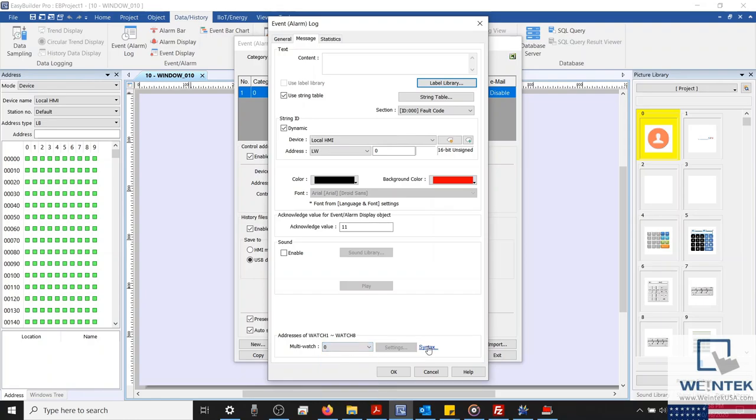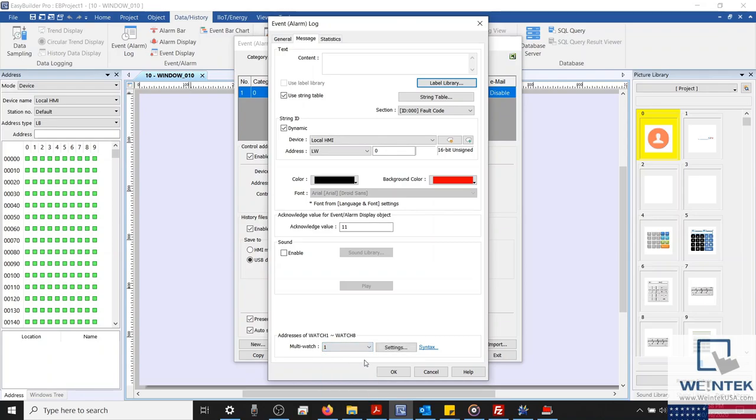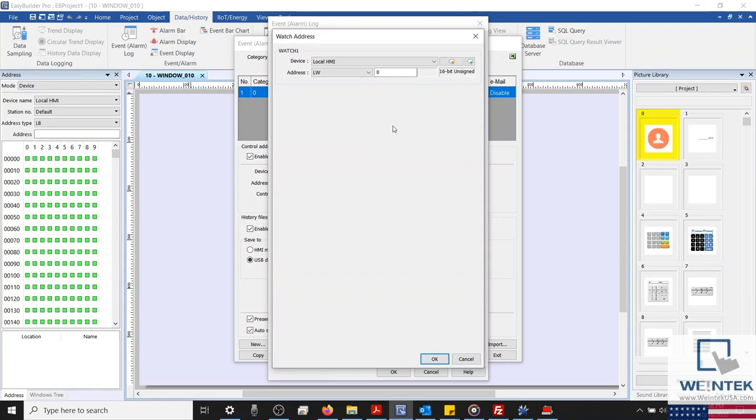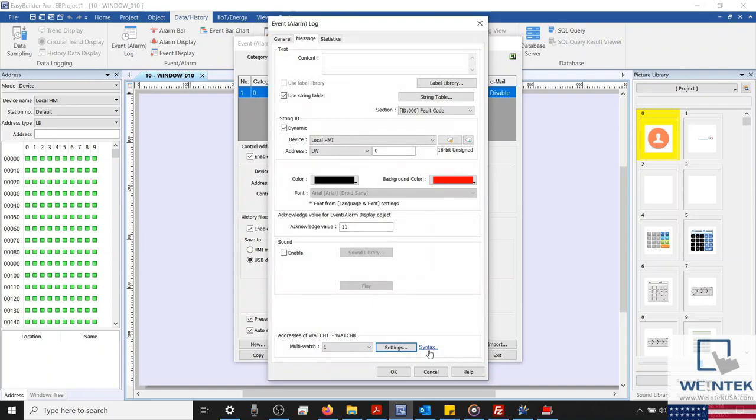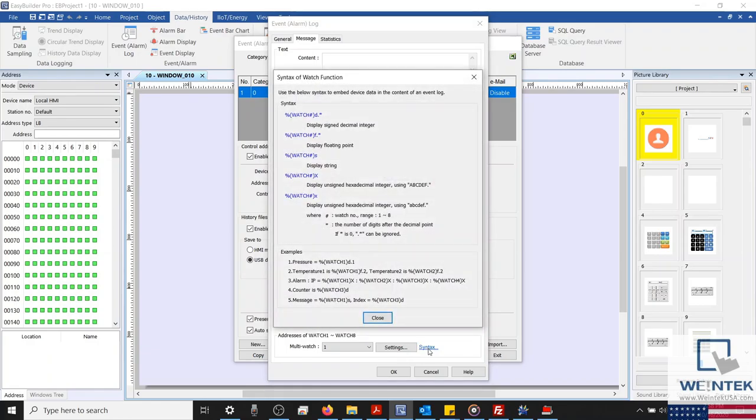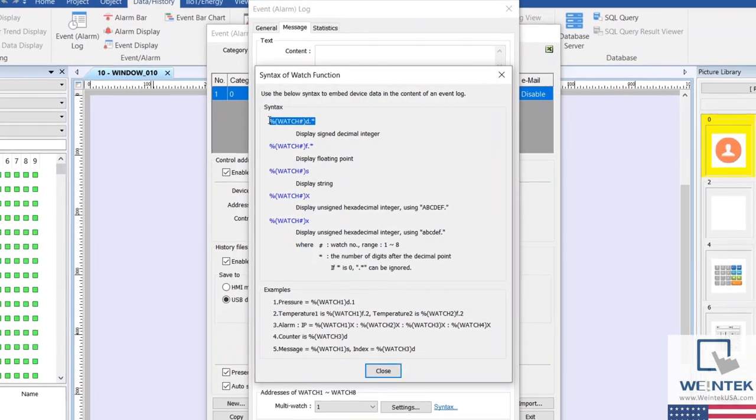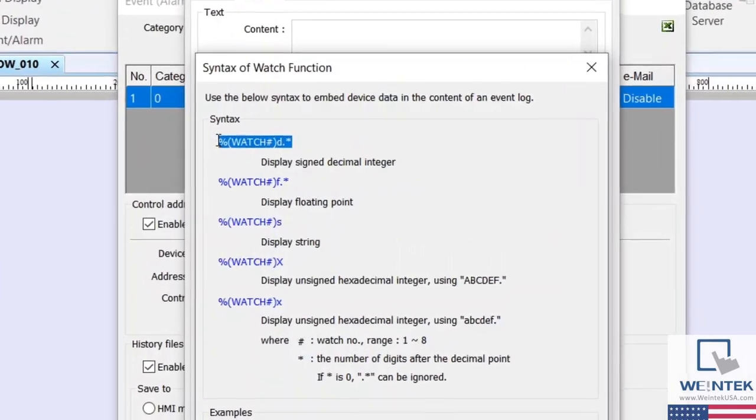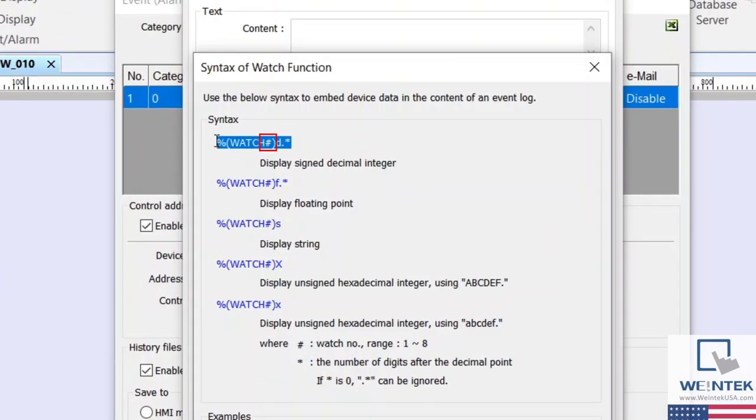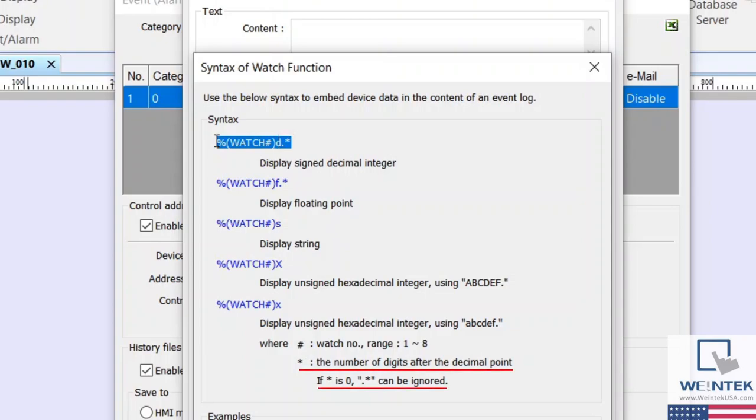Let's define a new watch address within our multi-watch list by selecting the drop-down menu and clicking 1. Now we'll click our settings button, and I'll configure my watch address to be LW0. If you recall, LW0 is used as the alarm's dynamic condition value. With our watch address defined, let's copy our syntax for a signed decimal integer. Within this syntax, the pound sign should be replaced with the number that corresponds with your watch address. The letter after the parentheses determines the data type of your watch address. And the asterisk can be replaced with a number that specifies the number of digits after the decimal point when reading numeric data.